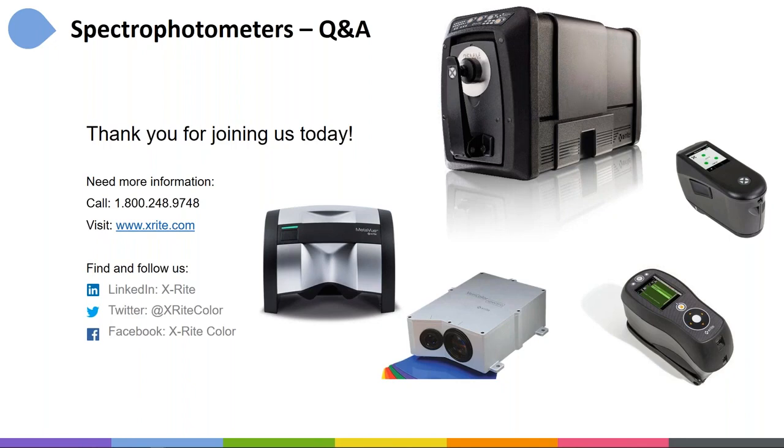Do the benchtops have D8 and 45-0 capabilities? No, they do not. The benchtop devices are all D8, all sphere instruments. One of the advantages of 45-0 devices is that because it's a directional light source, it is easier to do smaller spots. We have handheld 45-0 devices. The handheld instruments get used in the printing world a lot, because printers have to measure very small spots and 45-0 instruments do that really well.